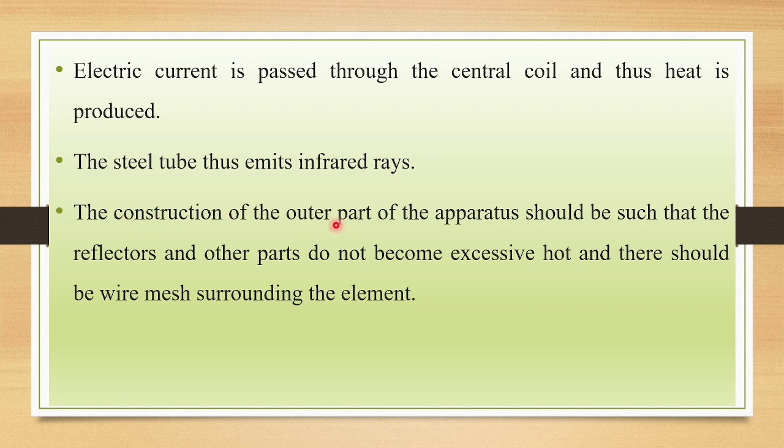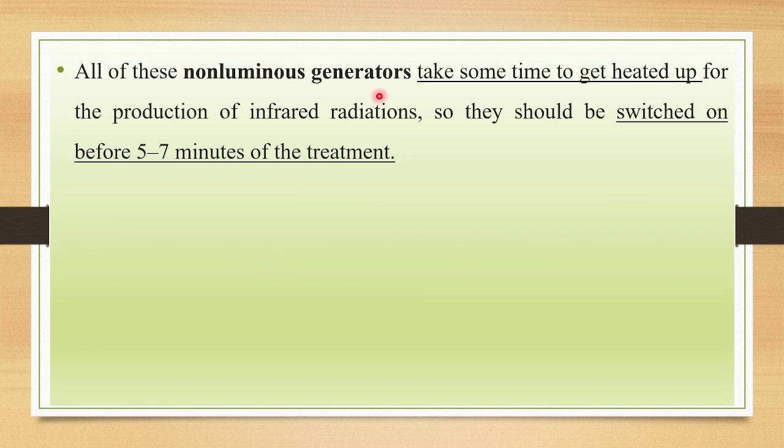The construction of the outer part of the apparatus should be such that the reflectors and other parts do not become excessively hot, and there should be wire mesh surrounding the element. So all of these non-luminous generators take some time to get heated up for the production of infrared radiations. So they should be switched on 5 to 7 minutes before the treatment.